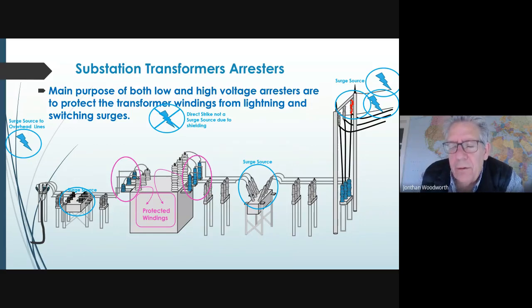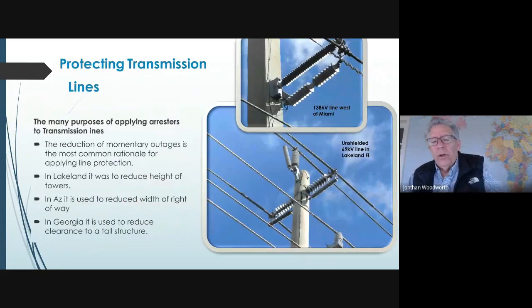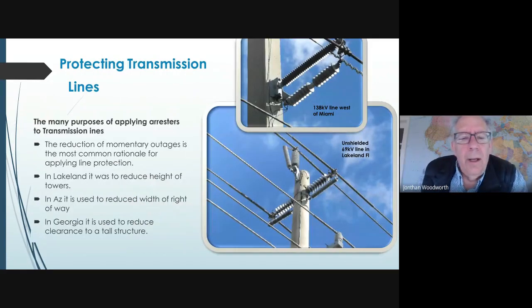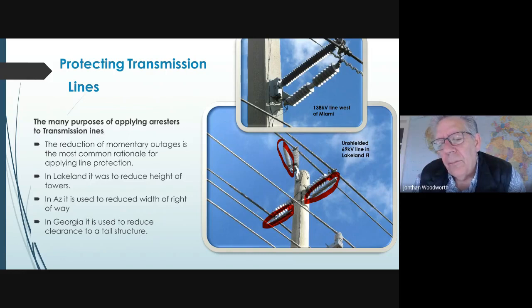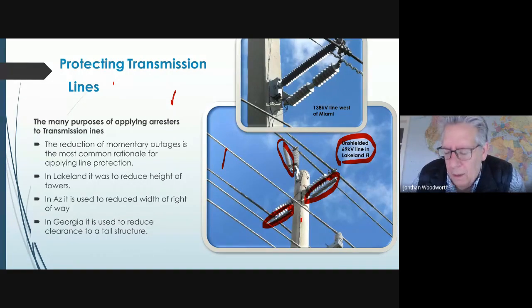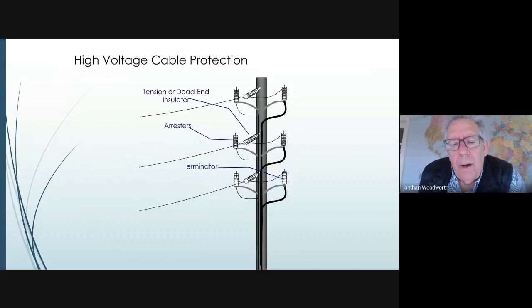Oops, this is the same slide, just differently. Here's some real world images of what it might look like. This is a 69 kV transmission line, and there's 3 arrestors up here, one on each phase, and there's no shield wire on this system. So this is an unshielded 69 kV system, and arrestors are put on every single pole all the way through the whole system. In the city of Lakeland, they have about 200 poles, so there's arrestors on 200 poles. High voltage cable is another area where there's a lot of protection needed.